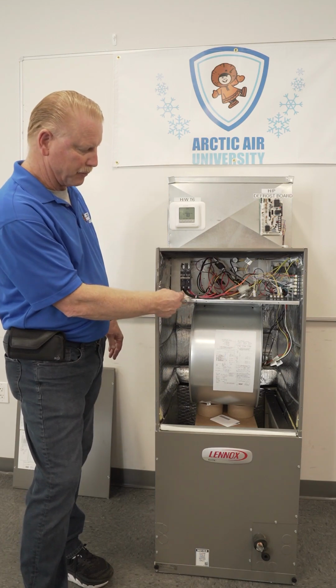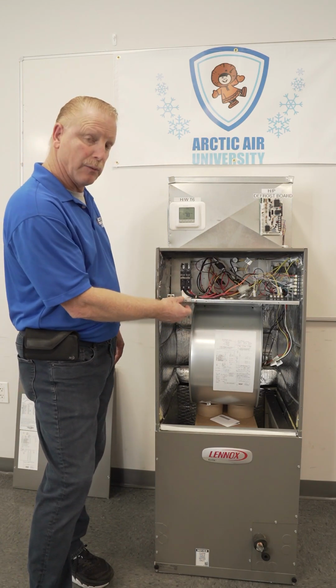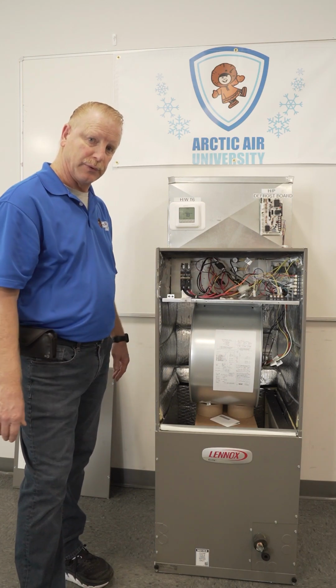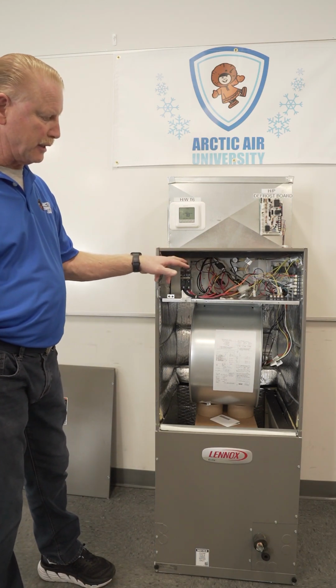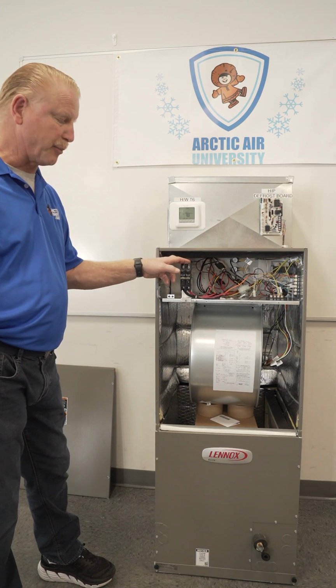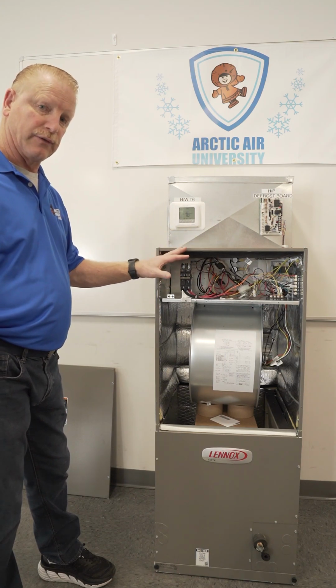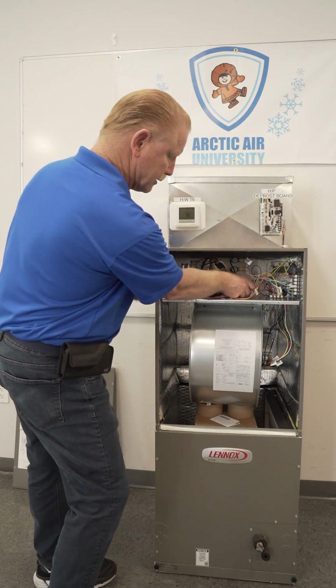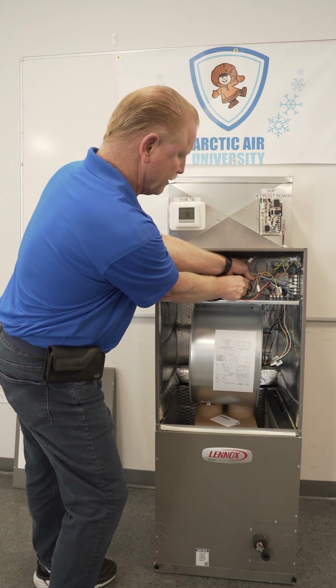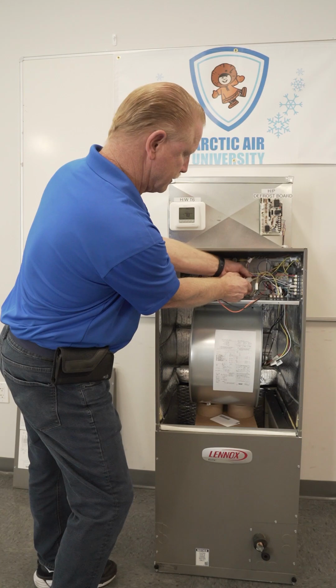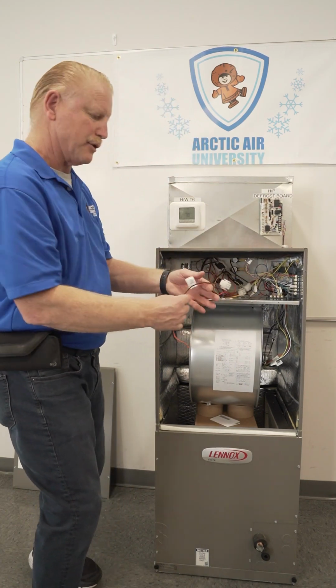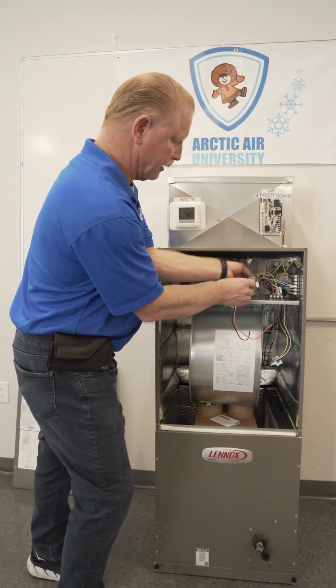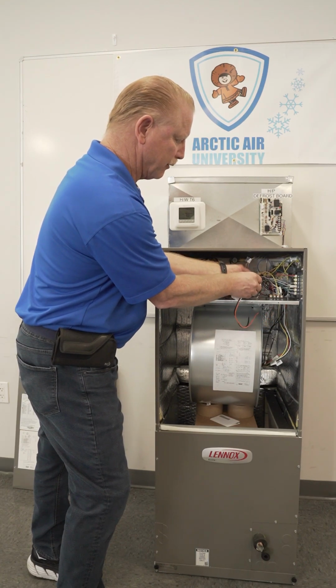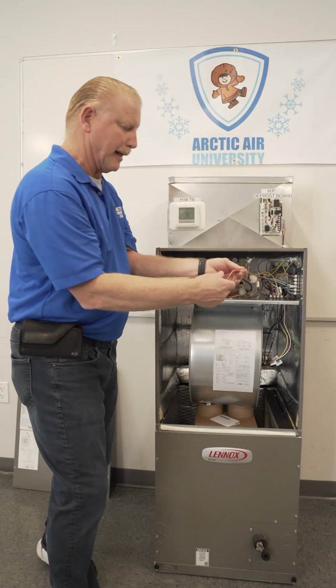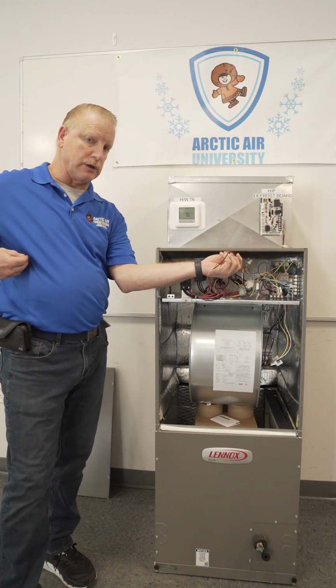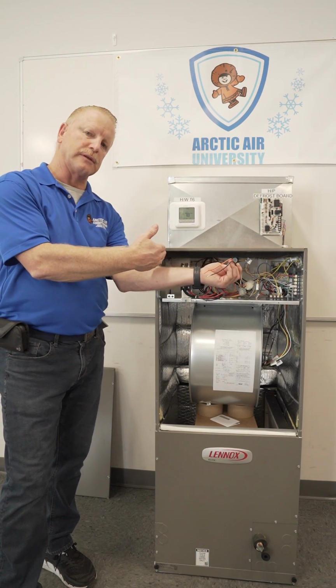You're gonna take that with the screws that are provided and put it in one of these holes and it's secured in place. Now you bring your line voltage in to the top of the circuit breaker and you're ready to go as far as line voltage. Your unit is going to come with a plug. Give me a second here to unplug this. This unit comes plugged in for a regular air handler, not ready for strip heat like this. This is where your line voltage would go and hook up to the system.